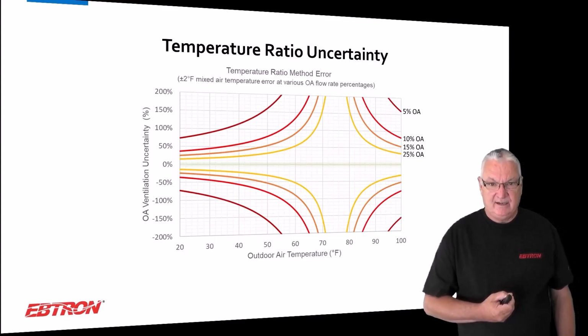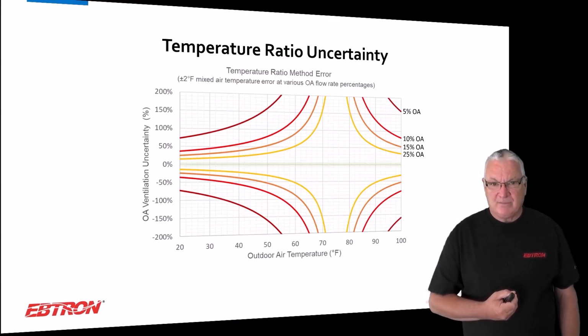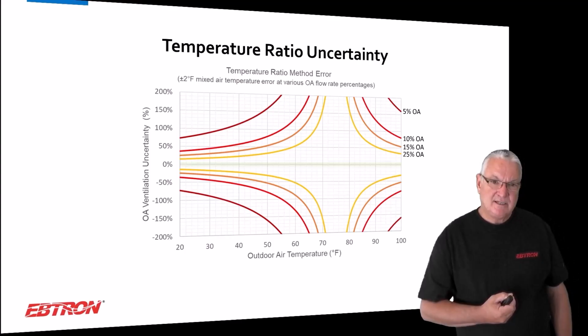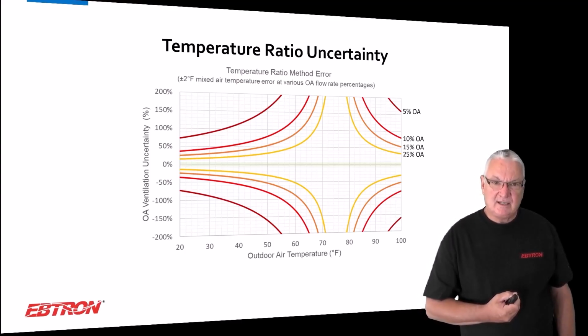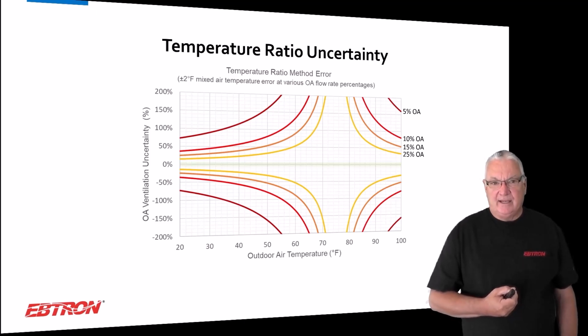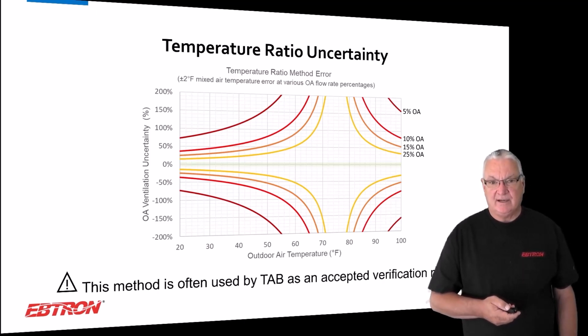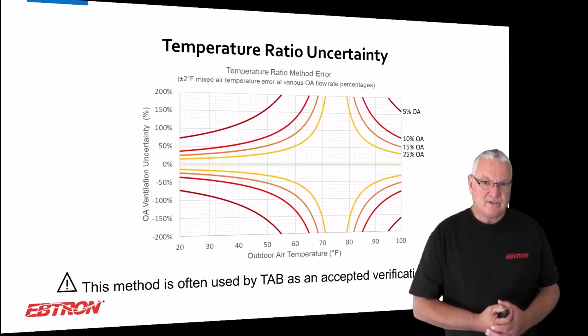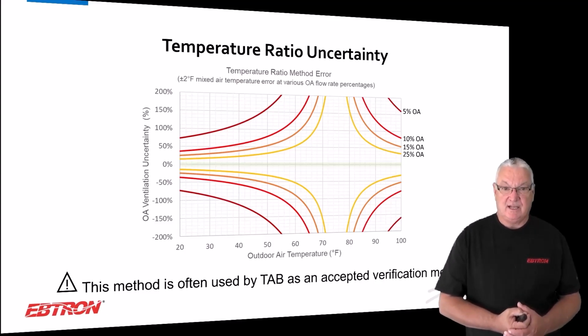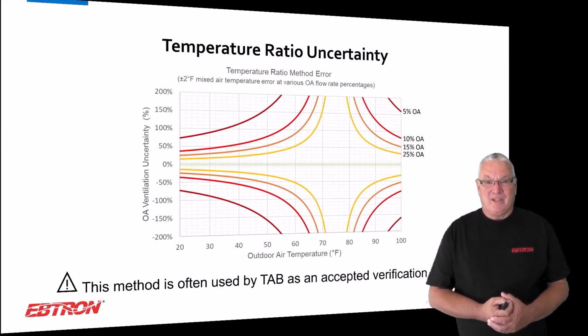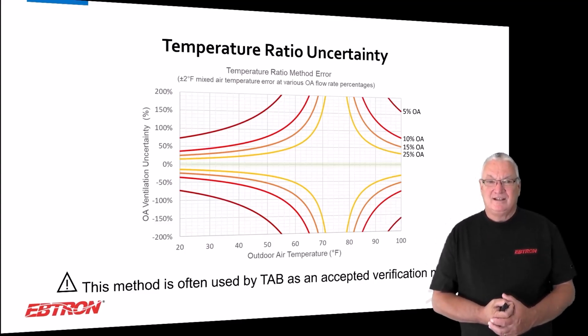You see the little green, it's really small. That's plus or minus like 5% tolerance on the outside air. And obviously, that's not where you're at. And so the method is really terrible. I tell test and balance folks they shouldn't use it because Standard 111 has this in there, and Standard 111 for test and balance professionals says you can be within 10% doing this. And it's not true. You can't. You'd have to be very lucky to be that accurate, and I don't like to go with luck.